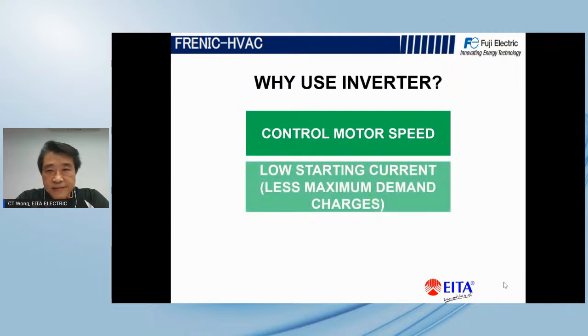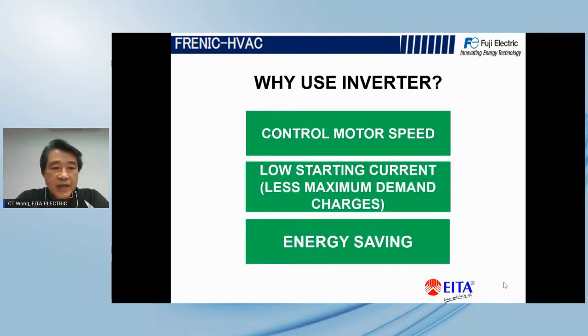Why inverters? I think everybody interested in this topic finds it very important. If, for example, you have a pump, should you put in an inverter or not? What are the criteria we need to consider? First, does this pump need to control the speed, or be able to vary the speed? Are you looking for low starting current, and also energy saving? Those are the important criteria.